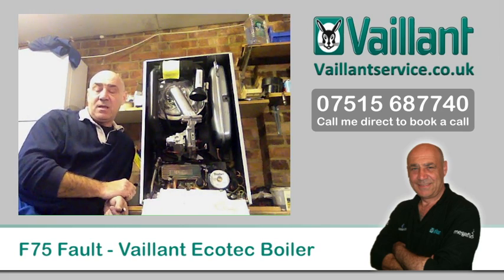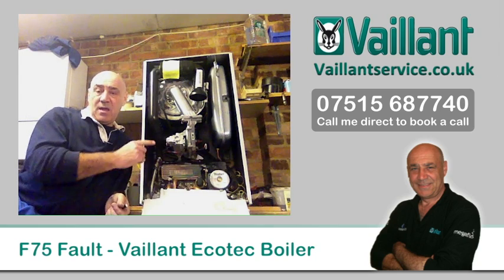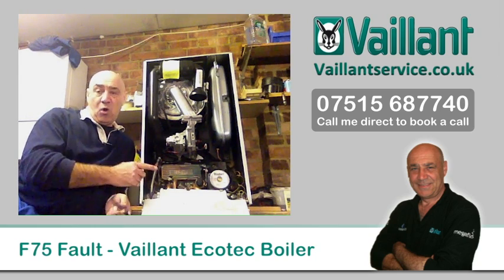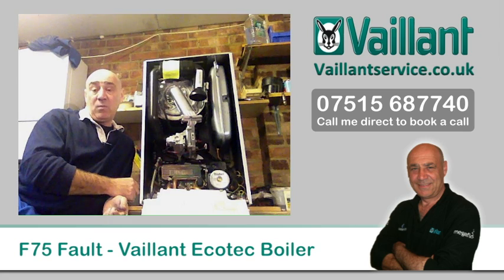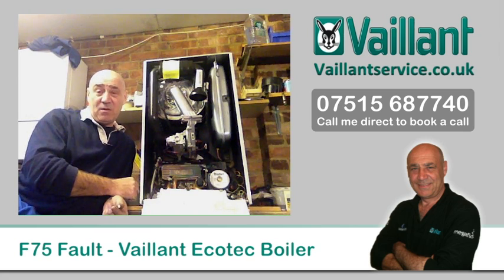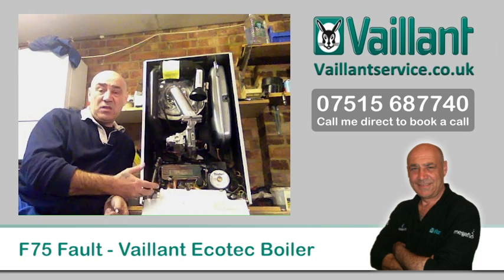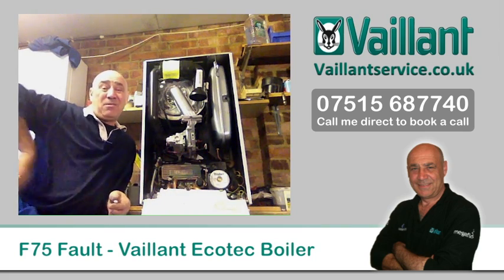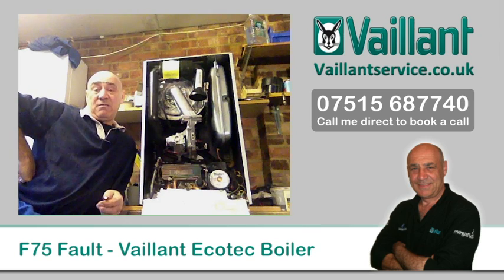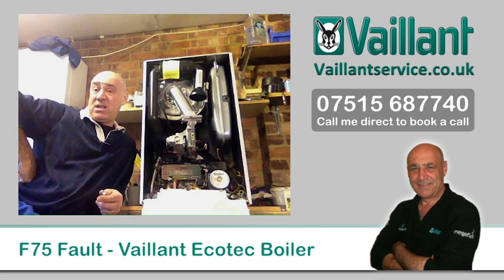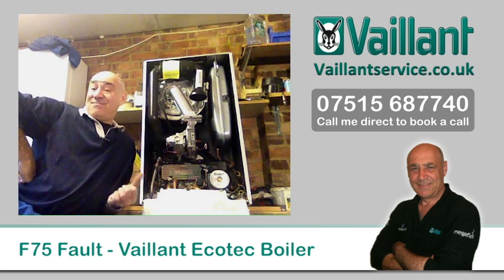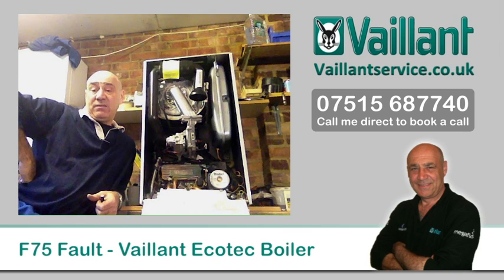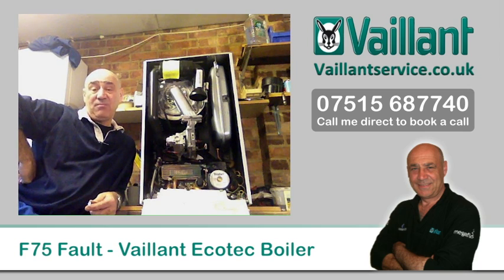Everyone's happy. Unless, of course, it's not getting that message, or it's not picking up that 0.1, 0.2 bar pressure increase. In which case the boiler will attempt to fire up or attempt to run 2 or 3 times, and then after a bit it will go, you know what, I'm a bit fed up with this, so I'm going to go and watch I'm a Celebrity, Get Me Out of the Jungle, or whatever it is. So it will just sit there and go, nah, no more, F75, and switch off, leaving you very cold and with cold showers. So, not good.